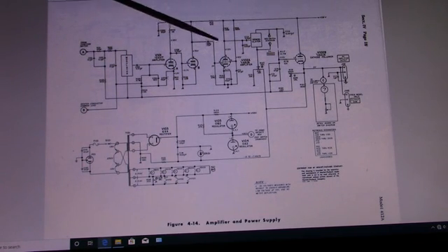And this is basically an AC coupled amplifier chain that amplifies that signal. In the last stage here, this is a pentode tube. The signal from the plate is applied to the demodulator, and of course the demodulator and the modulator are synchronized together so that this converts the signal back to DC at this point. From the demodulator, the signal is amplified in this cathode follower here. The output is tapped off the cathode and it's supplied to the terminal on the back, which provides a DC voltage that can drive a chart recorder or some other device.